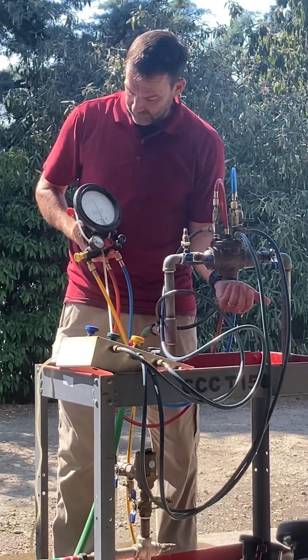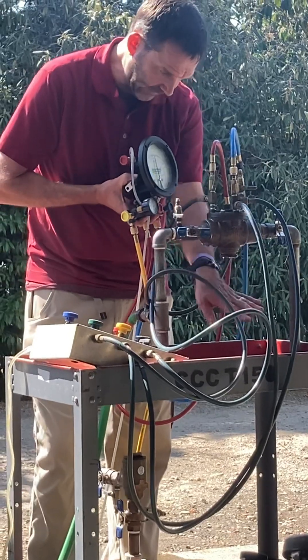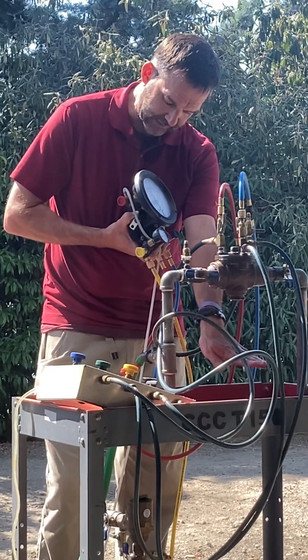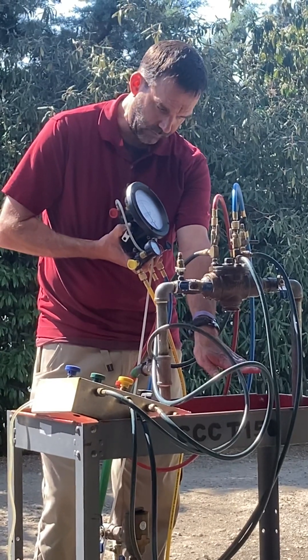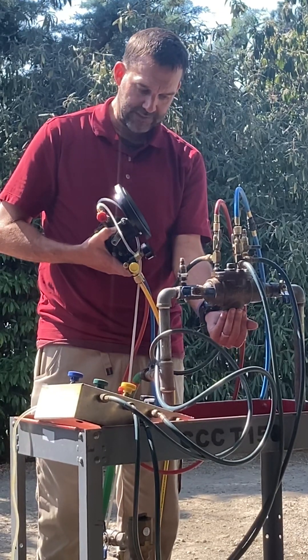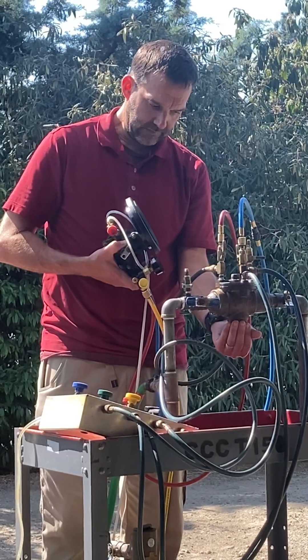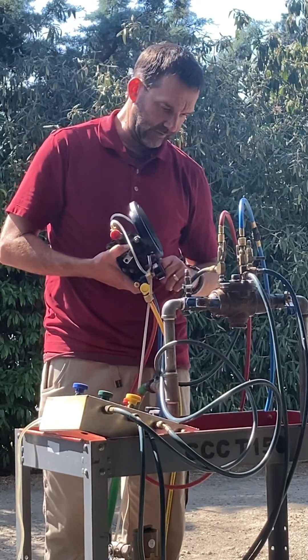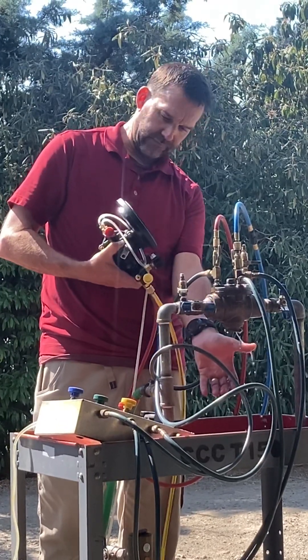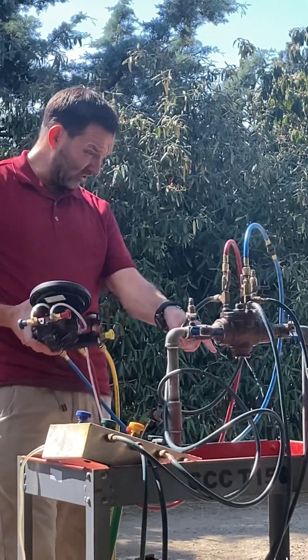8.7, 8.7, 7.4, 7.2, 7.0, 6.8, 6.7, 6.3, 6.2, 6.0, 5.8, 5.7, 5.6, 5.5 — there it is. Right there. I can even see it. The relief valve opened at about 5.4, and it's opening.